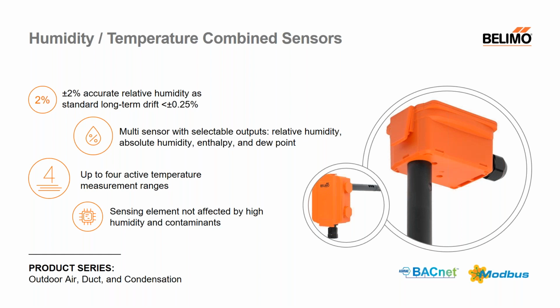On top of relative humidity, Belimo's humidity sensors also measure absolute humidity, enthalpy, and dew point. These values are all field selectable on the unit itself and are included in all of our humidity sensors as standard. When it comes to the temperature side of our humidity sensors, we have 4 selectable measurement ranges, which also makes it easier for our customers to choose part numbers and hold stock. This allows our customers to effectively order one part number for various zones within their facility.